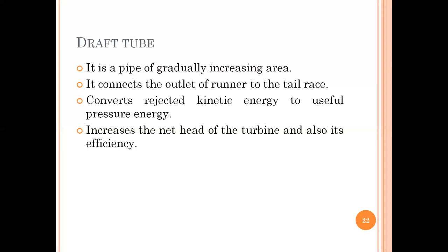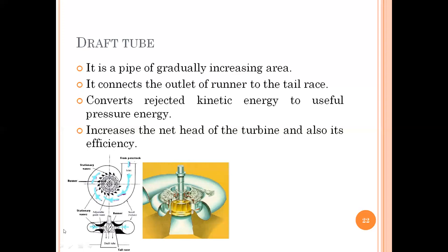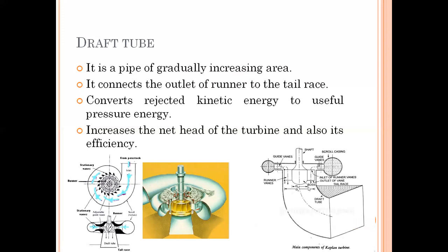One type of draft tube is conical — straight down — used in the Francis turbine where water goes around and then comes down through the turbine. The other example is the Kaplan turbine draft tube, which has a circular section at inlet and rectangular at outlet. In both cases the area is increasing from section one to section two, and both are below the tail race level.